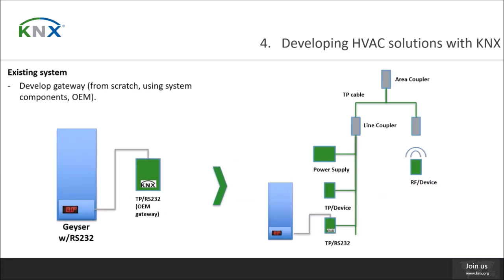What about existing systems or standalone systems that we already mentioned, like a boiler or a geyser? You can develop a device for direct communication with KNX as described before. For instance, a piggyback KNX board for your existing electronics. But you can also create a gateway if your solution already has basic serial or IP connectivity. In the example on the slide, you may have a geyser which already has RS-232 connectivity. You could use an existing OEM gateway from RS-232 to KNX twisted pair, and you can bring your geyser into the control of the KNX installation.